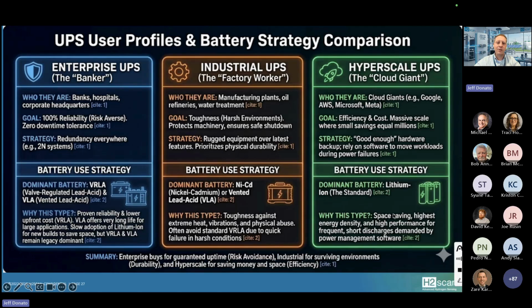The second one I'll address is the industrial market. This would be the factory floor, with UPS backing up processes in manufacturing plants, refineries, water treatment plants, and similar applications. They are typically in harsh environments, and you might find vented batteries like nickel cadmium or vented lead acid batteries backing up important processes.